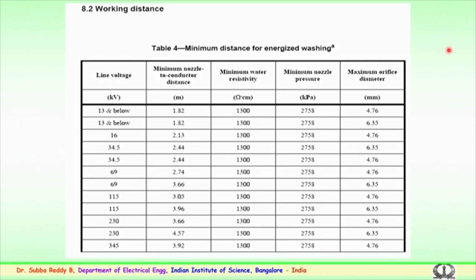This table gives the information about the minimum distance where a personal or the cleaning is to be done, in particular during the energized washing or cleaning conditions. The working distance, minimum distance to be employed here. Earlier also we have looked into this similar arrangement. So, depends upon this gives the line voltage for various voltage levels. This is the minimum nozzle to conductor distance for the cleaning, minimum water resistivity, the minimum nozzle pressure to be adopted, and the maximum orifice or the diameter in millimeters.